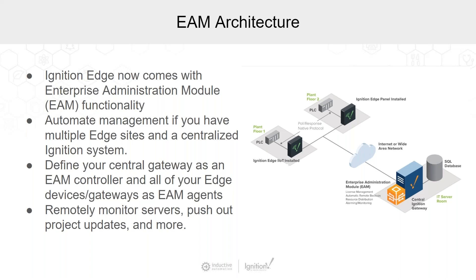This is a huge value add for people who have standalone panels or data collectors out there. Every time you need to upgrade those, instead of having to log in to each one individually, you just log in to the central gateway, create a task, push it out, and you're done. Or if you need to onboard a new device, it automatically takes backups — you just plug in the new device, connect to the central Ignition Gateway, and it can restore the backup and get running. So it's super valuable to have this Enterprise Administration Module.